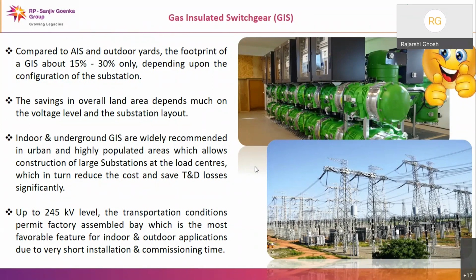And in Kolkata we have one substation where in the first level down, that means at -1 level, we have a 33 kV GIS, and at -2 level we have a 145 kV GIS. So it is an entirely underground substation with EHT, EHV equipment, and normally cables come from the bottom for the termination. Here the cable came from the top to terminate on the GIS board. Now up to 245 kV level, the transportation conditions permit the factory assembled bay, which makes it very easy to install and gives very short installation and commissioning time.